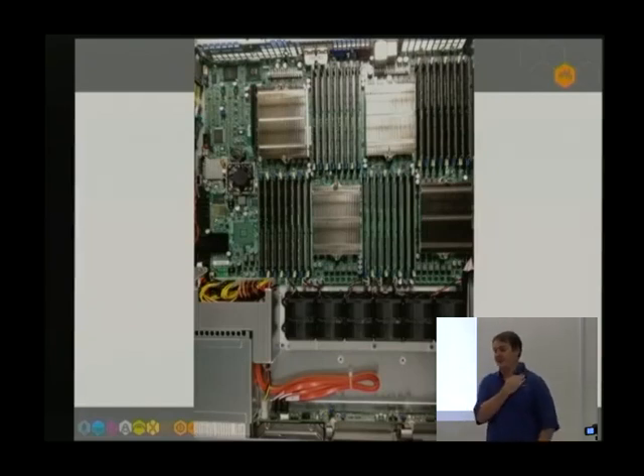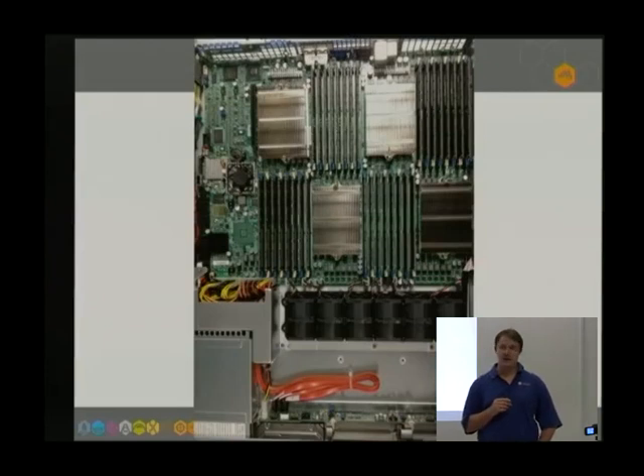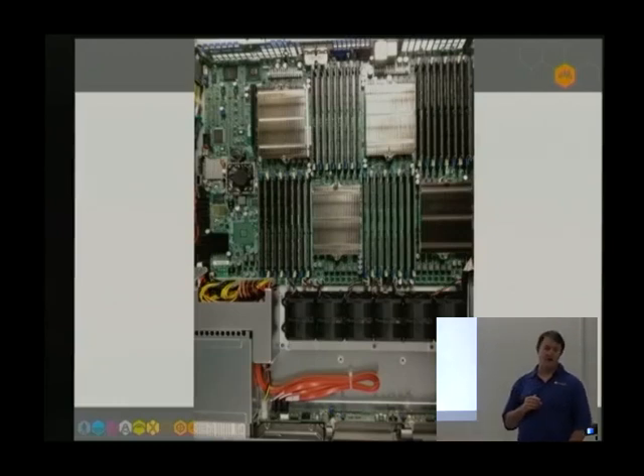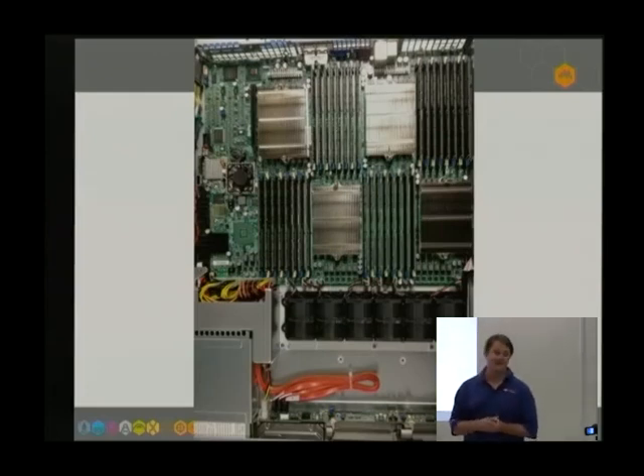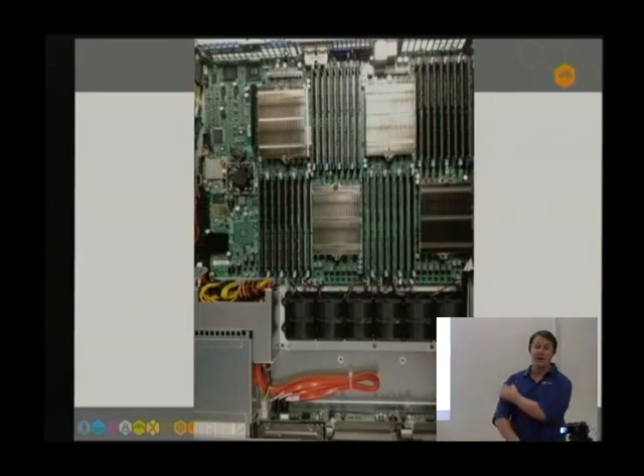The other great thing, which unfortunately we've had to do, we control the speed of these things quite carefully in the case when a chiller fails. Our room goes from a nice balmy 22 degrees to about 70 degrees in the space of about 3.5 to 4 minutes when you don't have a chiller running. And when it's that hot, hypothetically speaking, you can't touch the buttons on the nodes. They're too hot with your fingers. So you have to use screwdrivers to turn your nodes off. Not a lot of fun, believe me. But yes, we now quite accurately control the gigahertz of these things. So if we have a system failure in the cooling systems, we clock them down very rapidly.